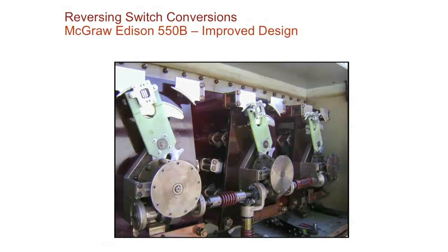That's what it looks like inside the unit. There's a 3-phase unit putting it in service. And here's what some of them look like when we get to site and look at the LTC. You can see that you got a lot of coking going on. There's basically tracking almost going on from here to here continuously. So basically this is becoming a current carrying capacity where we don't want that going on. And that's how you end up with failures inside LTCs.